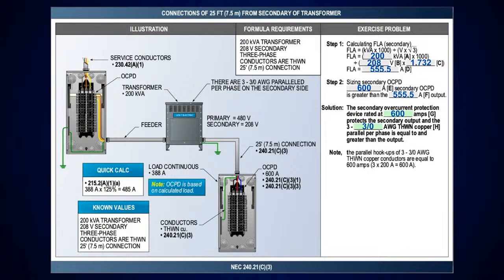Well, a 3/0 is good for 200 amps. So three 200 amp parallel conductors is going to give you 600 amps. And if you notice, did I change the calculation? No. The calculations have to stay the same. You have to be careful because if you all of a sudden at the end of your statement put in an adjustable circuit breaker, then you're going to have to change your equipment ground.